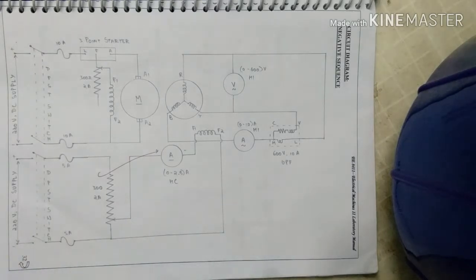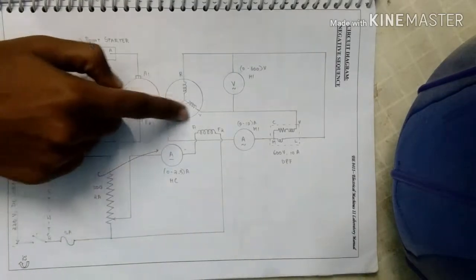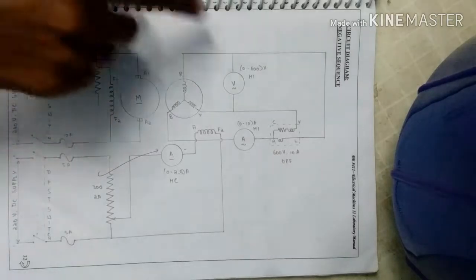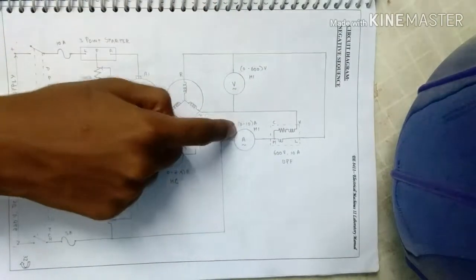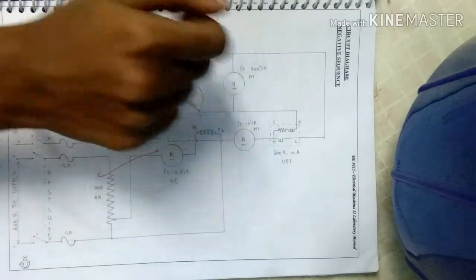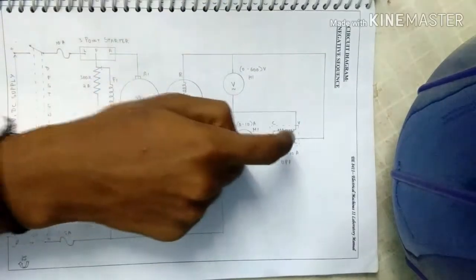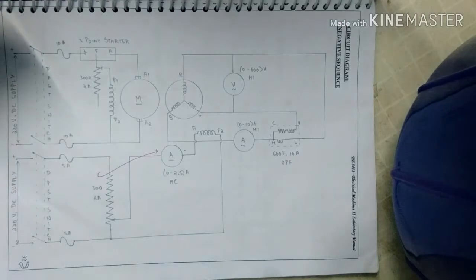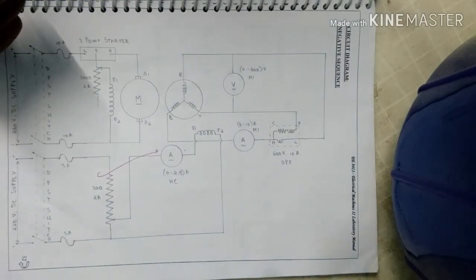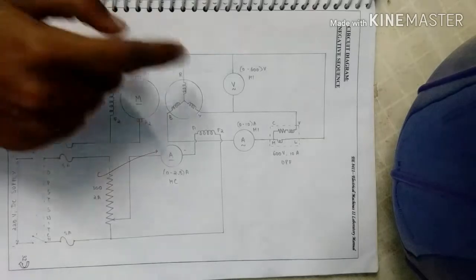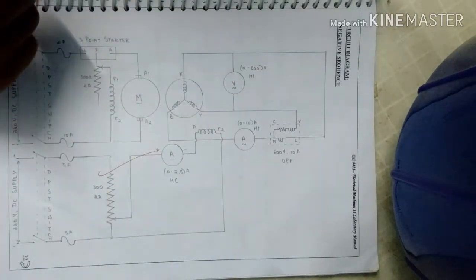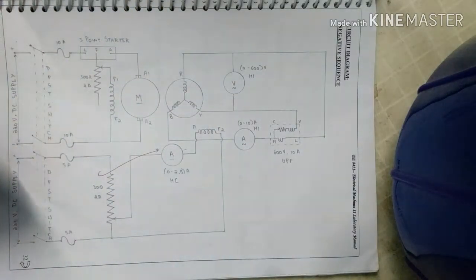The procedure for negative sequence: run the machine at the rated speed, short circuit the two phases of the alternator through an ammeter and the current coil wattmeter. Connect the voltage coil of the wattmeter and voltmeter between open phases and short circuit phases. Gradually increase the excitation such that the short circuit current does not exceed its rated value and tabulate the readings.